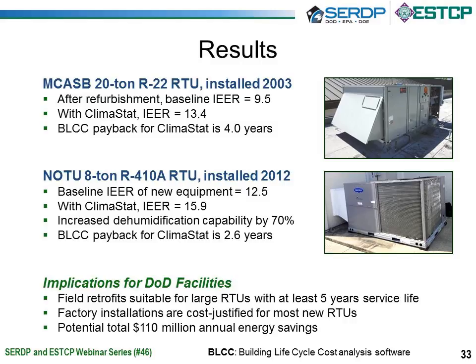For DoD facilities in general, the field retrofits are suitable for large RTUs with at least 5 years of service life left. Factory installations are cost justified for almost all new RTUs, and potential total of $110 million savings across all DoD facilities.